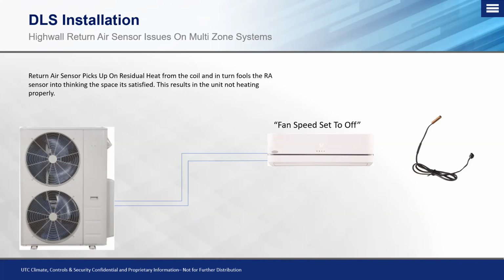And it's all of about 3 to 4 inches away from that indoor coil. So if you were to just shut the fan speed off and not relocate the return air thermistor, what would happen is that refrigerant flowing into the indoor unit, which we talked about as that minimum refrigerant flow or oil return, we're not changing that. That coil is still going to get hot. We shut that fan speed off, and now that residual heat is going to come up and hit that sensor, and it's going to go from overheating to not heating at all because that sensor thinks it's 85, 86 degrees because of the residual heat that's rising off of the coil now because we shut the fan motor off.